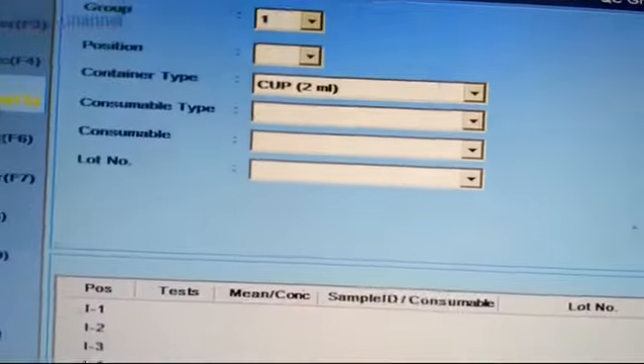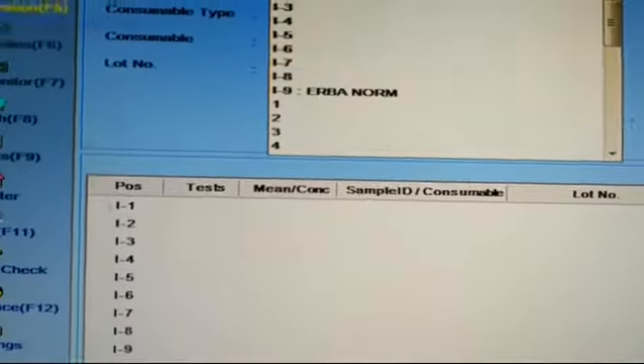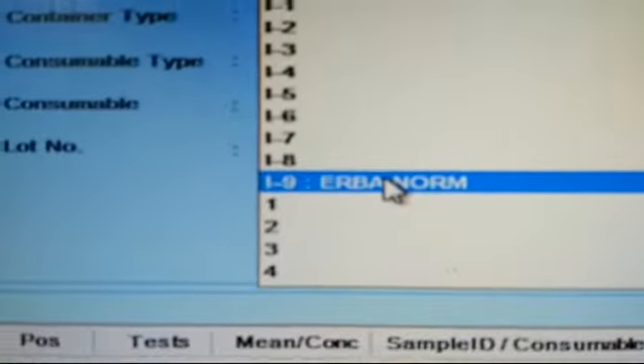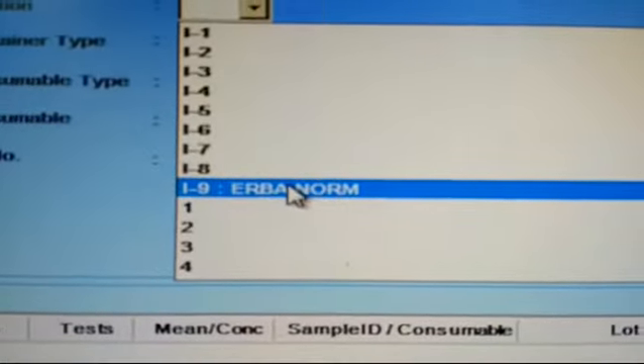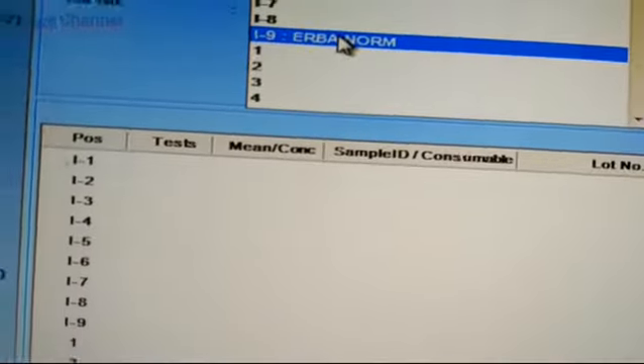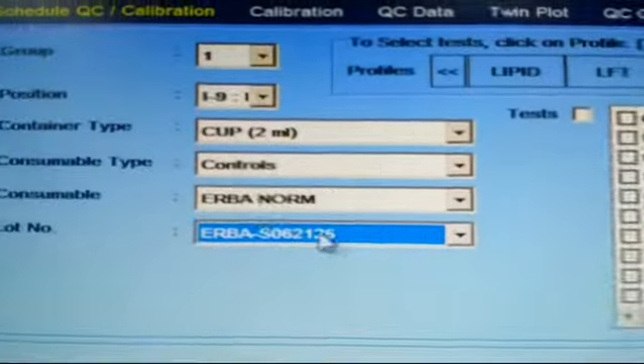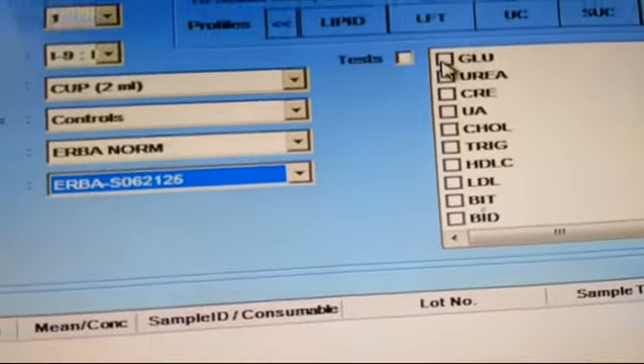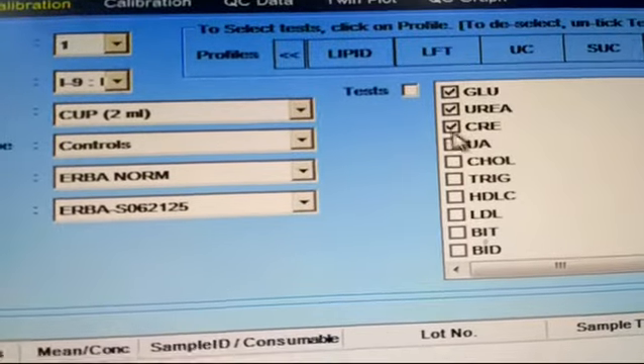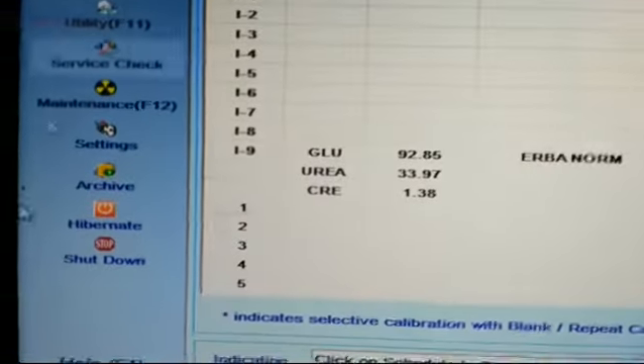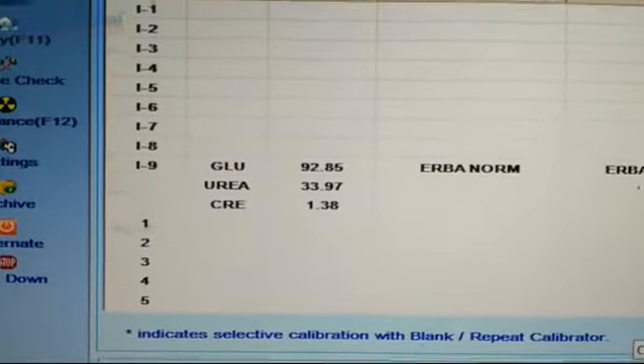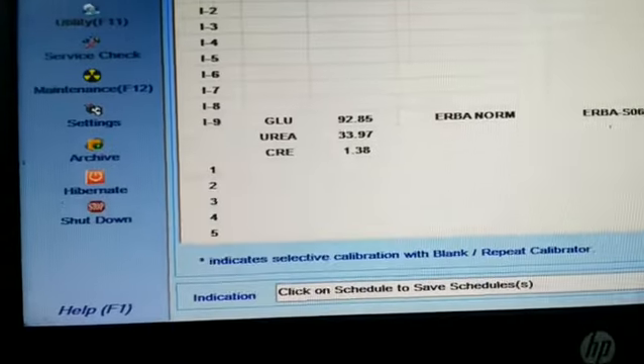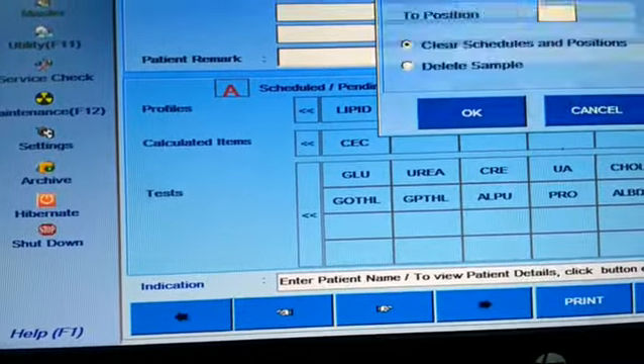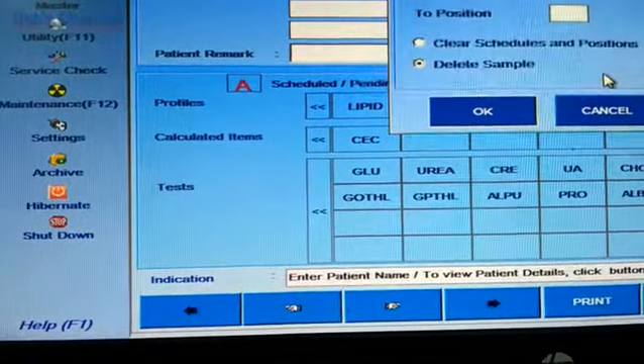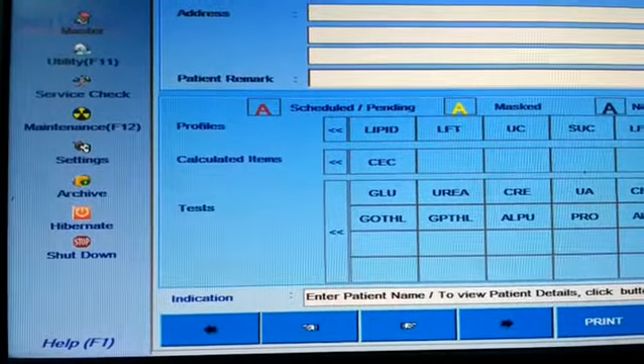Whenever we run the control and calibrator, we have to go to control and calibrator. Then we have to select the position, like the I9 position is the ERBA norm control. We select the ERBA norm control, then we select the tests for the control run, like glucose, urea, creatinine, etc. After selecting, we press OK, and then we schedule the programming. After that, if we press the start button in the status monitor, the program will start. Okay, the machine is calibrated, so no need to run the control or calibrator right now.